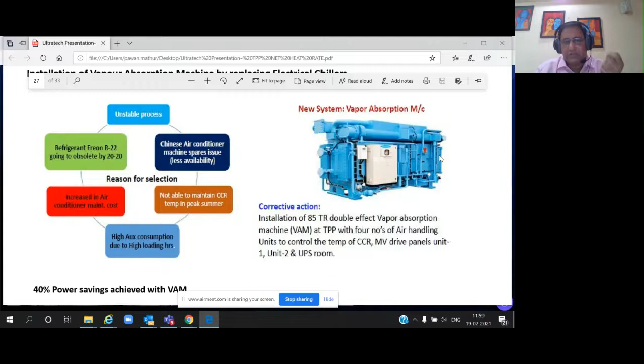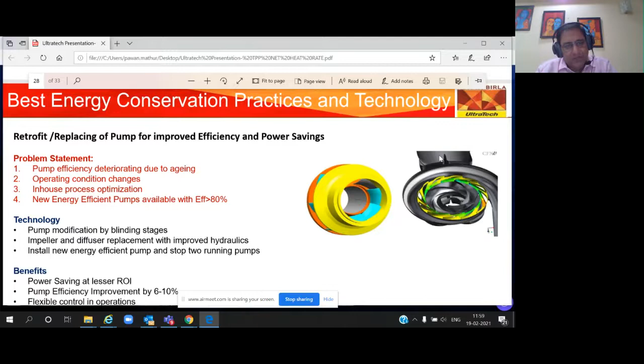One of the issues we are facing at many of our locations is that now solar is there, then WHR is there, so our PLFs are reducing. Hence the pumps, especially BFP pumps, are getting inefficient. So what to do about that? In one or two places we have done retrofitting of the pumps. By changing the pump internals or blinding the stage, we are making these modifications to bring the pump efficiency back to its desired value.